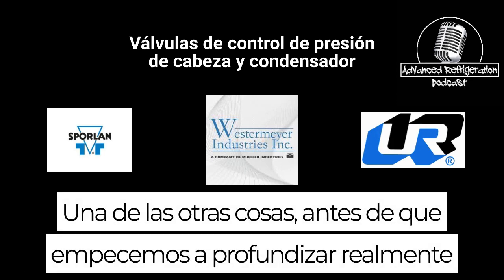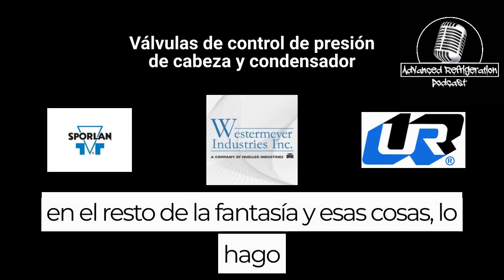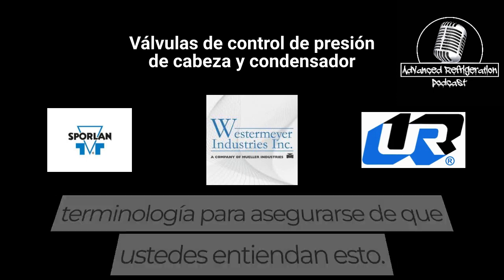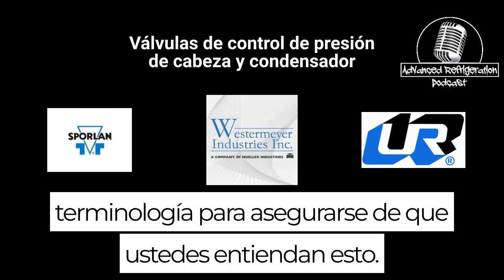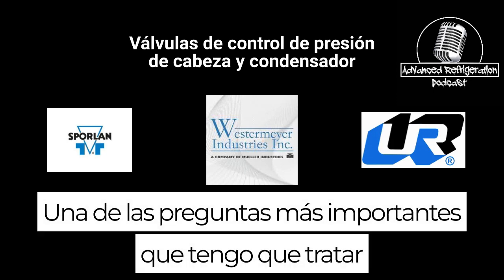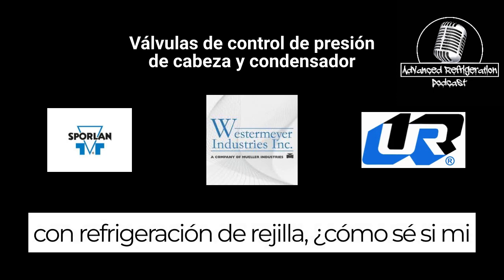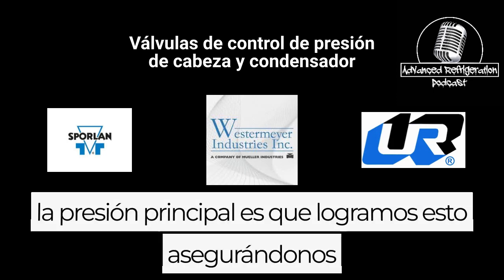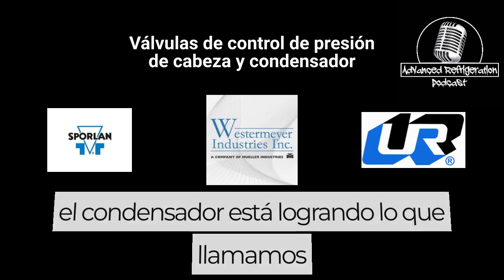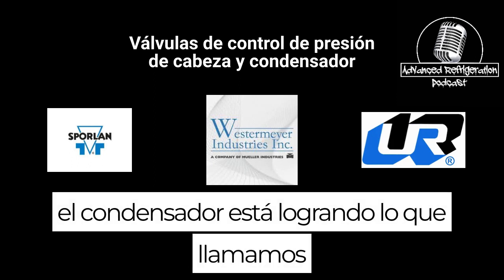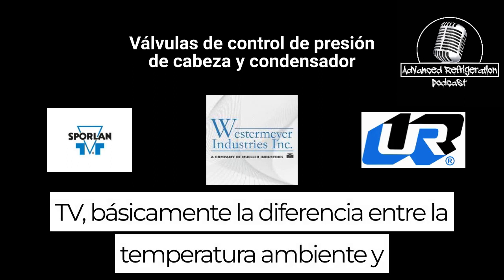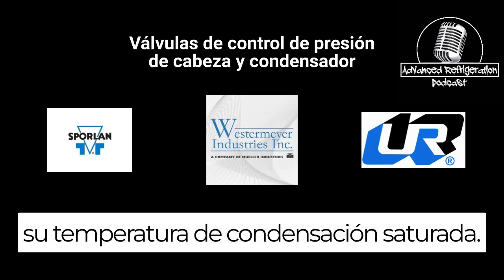One of the other things before we start really delving into the rest of the fan cycling and stuff, I want to go over some terminology to make sure you guys understand this. One of the biggest questions I get, especially dealing with rack refrigeration, is how do I know if my head pressure is right? We accomplish this by making sure the condenser is achieving what we refer to as TD, basically the difference between the ambient temperature and your saturated condensing temperature.